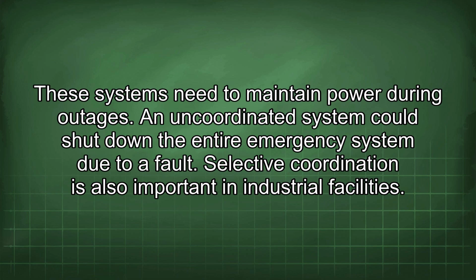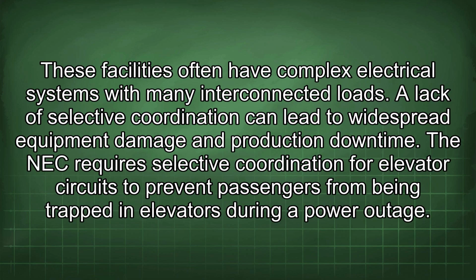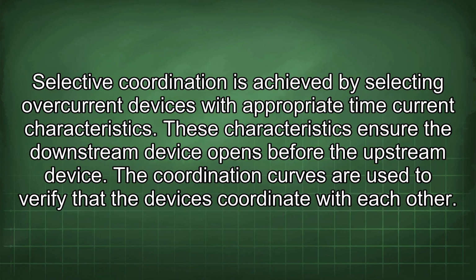Selective coordination is also important in industrial facilities. These facilities often have complex electrical systems with many interconnected loads. A lack of selective coordination can lead to widespread equipment damage and production downtime. The NEC requires selective coordination for elevator circuits to prevent passengers from being trapped in elevators during a power outage. Selective coordination is achieved by selecting overcurrent devices with appropriate time current characteristics. These characteristics ensure the downstream device opens before the upstream device.